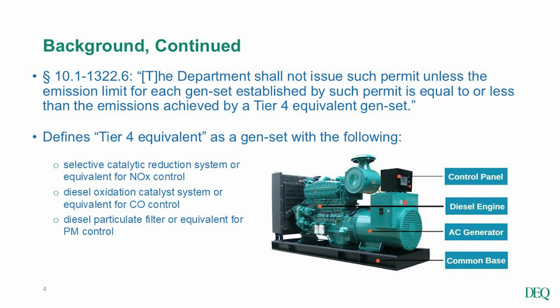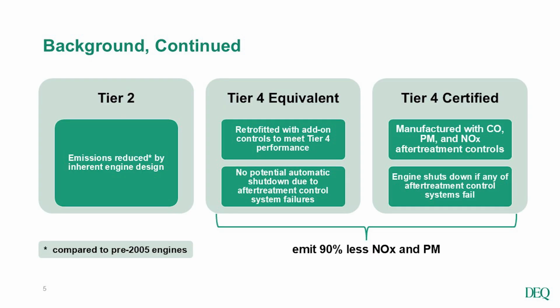This image that you see below shows the various components of a genset mounted together. We have the common base, the generator, the engine, as well as the control panel. This next slide contains a breakdown of the tier ratings for engines. In a Tier 2 genset on the left, you can see that emissions are reduced by inherent engine design compared to pre-2005 engines by using fuel injection and catalytic converters. On the right, you see Tier 4 equivalent as well as Tier 4 certified. Tier 4 equivalent is a retrofitted genset with add-on controls to meet Tier 4 performance, whereas a Tier 4 certified genset is manufactured with carbon monoxide, particulate matter, and nitrous oxide after-treatment controls.